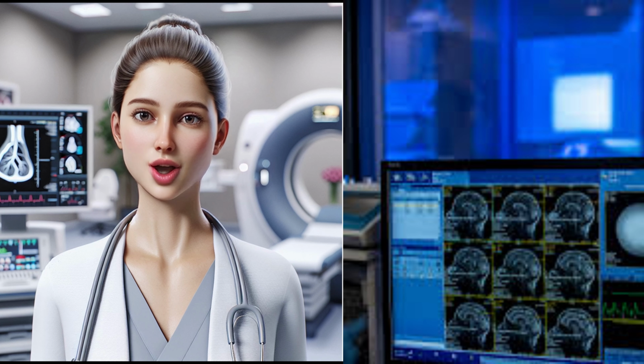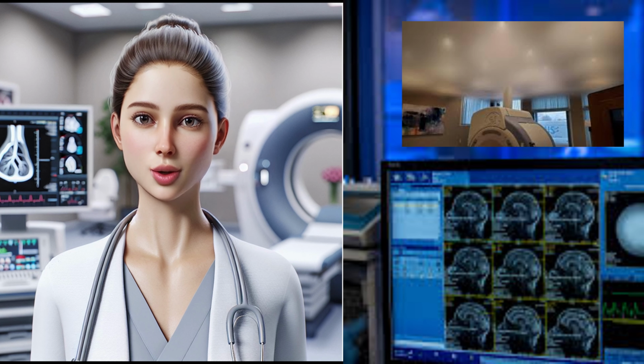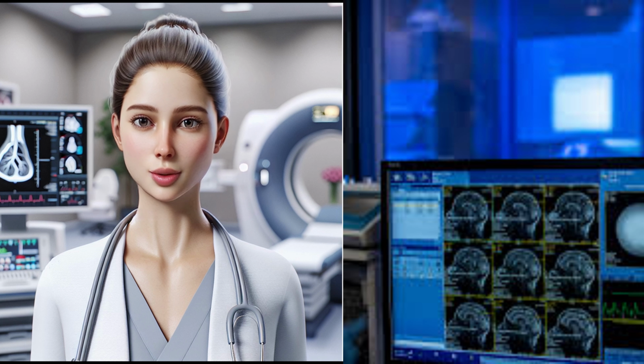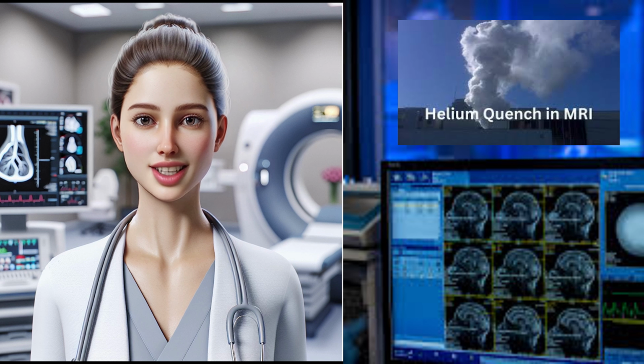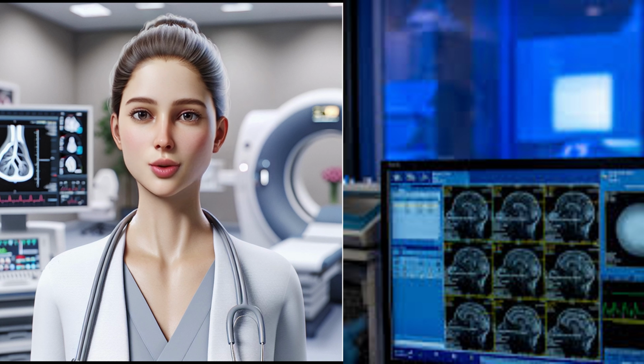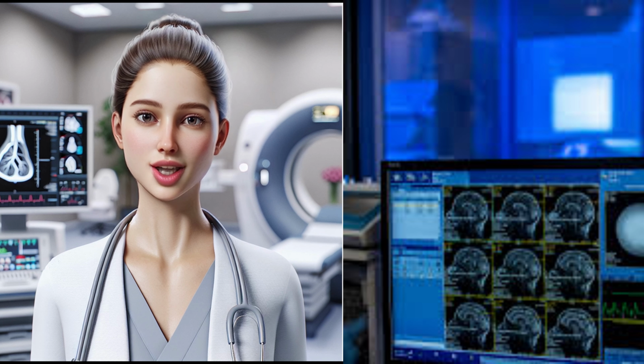What is an MRI quench? An MRI quench occurs when the magnet loses its magnetic field. This happens when the liquid helium used to cool the magnet turns into gas and escapes quickly into the air. A quench can occur accidentally due to equipment malfunction, or it may be intentionally initiated during an emergency, such as when a patient is injured or trapped near the magnet.